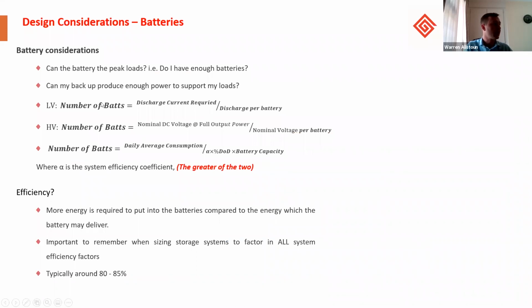So, can the battery deal with peak loads? Do I have enough batteries? Can my backup produce enough power to support my loads? And here are some simple calculations which I've put together, which can assist in the calculations. For low voltage batteries, the number of batteries you require is the discharge current required divided by the discharge per battery. This differs for the high voltage batteries.